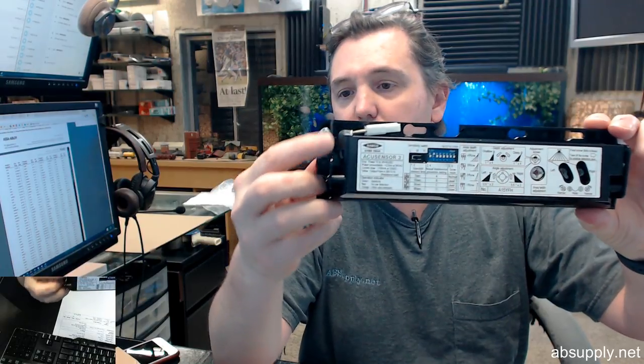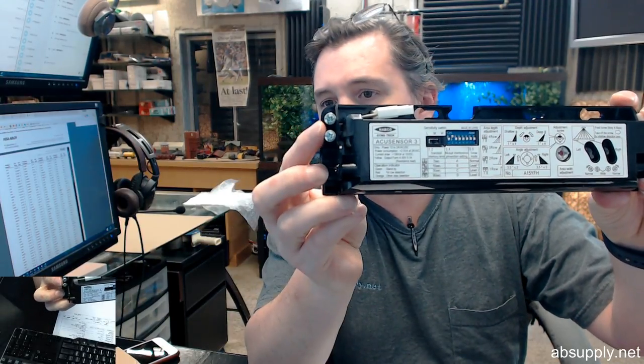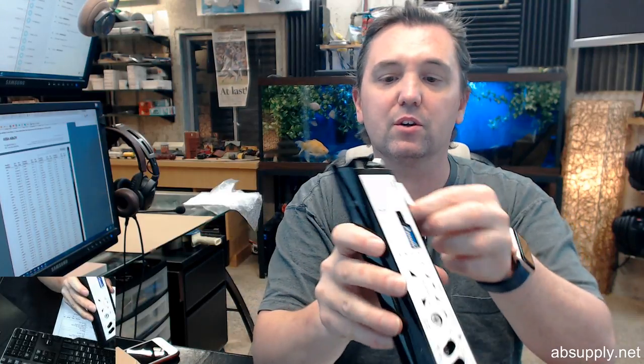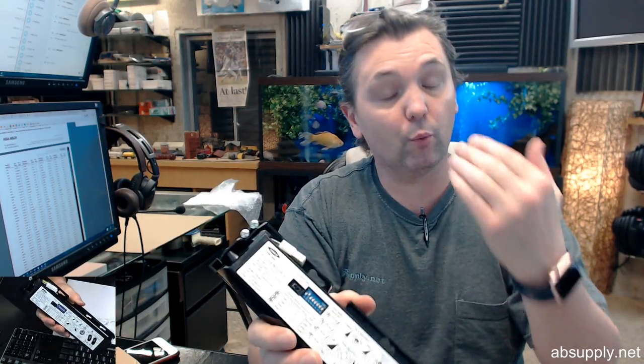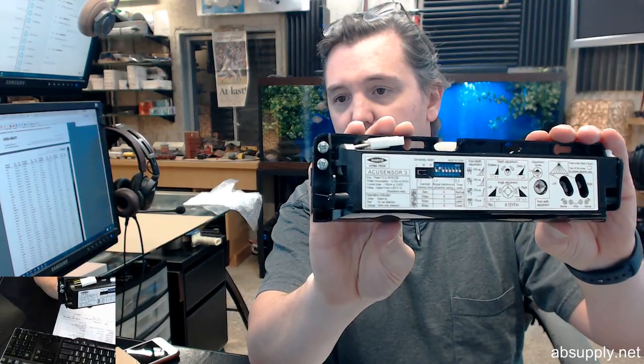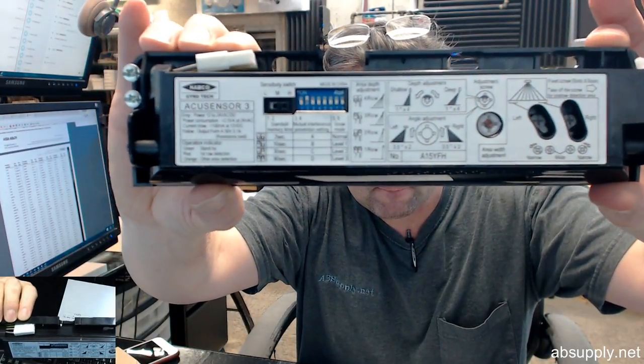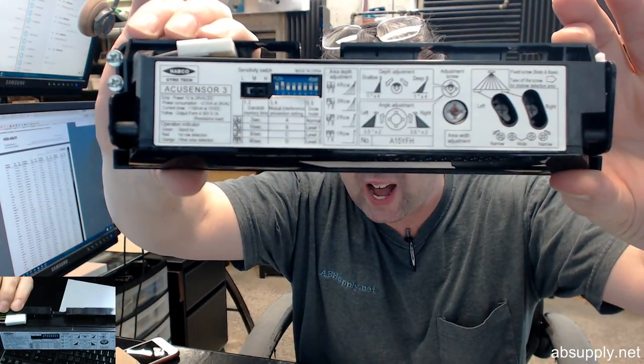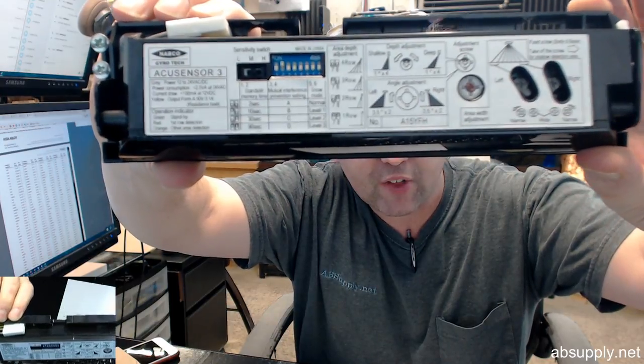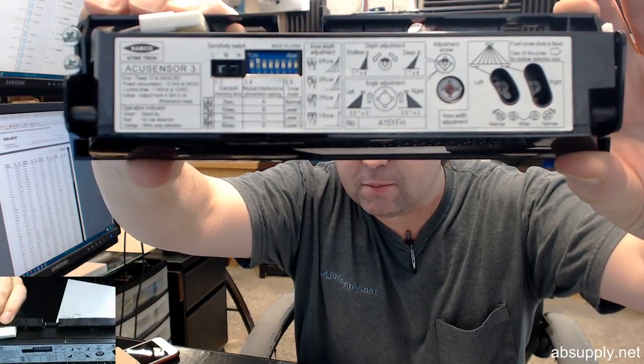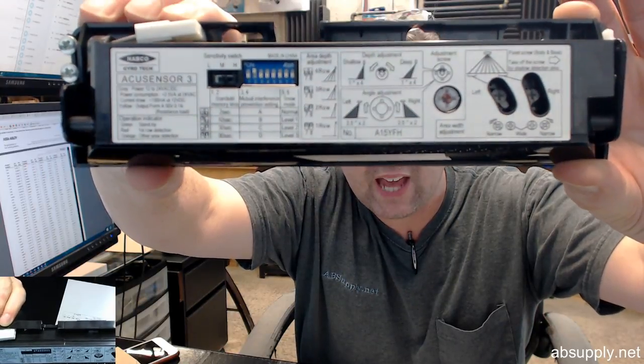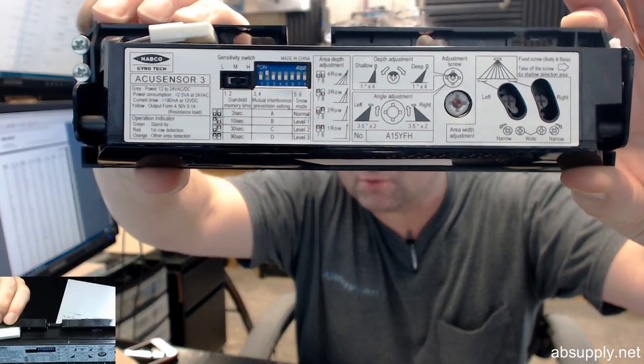So let's start with an identification of the parts. The mounting screws, part number 1, they're here. Part 2 is the connector, and that's obviously the way to communicate with the rest of the installation. 3 is your sensitivity switch, where it's set at the factory at medium, and you might need to adjust it low or high, and we'll talk more about that later in the installation instructions. 4 mounting holes, 5 dip switches. We're going to go over that in detail as well. 6 adjustment screw for the angle, that's important, with adjustment screws as well.